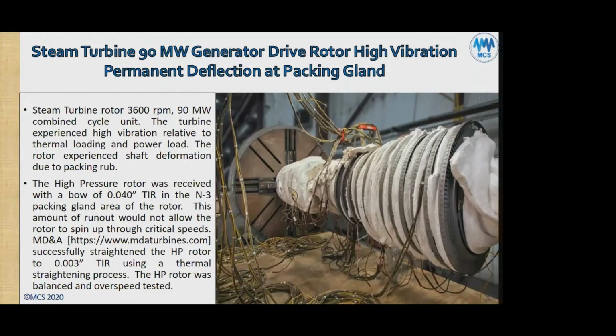The rotor was successfully straightened, and what you see in the picture are thermal heating resistance wires, insulated with the white insulation blankets that you can see. They have to heat up the rotor, and then they will straighten out the bent part. Typically, they'll try to heat it first, and we're talking very high temperatures. They have to heat it to at least around 1,000 degrees Fahrenheit, preferably no more than that.